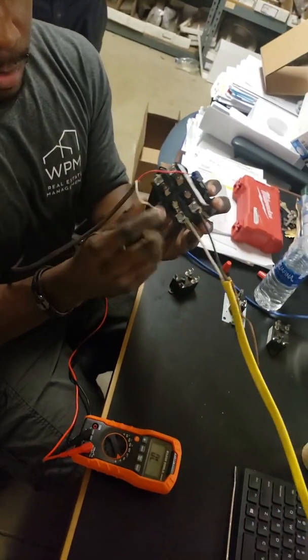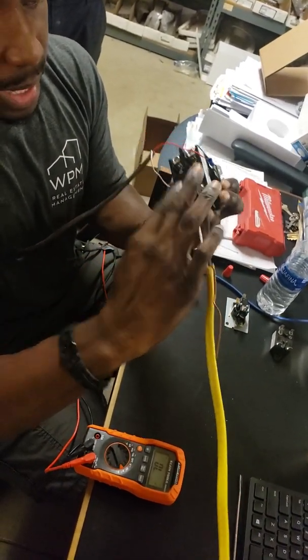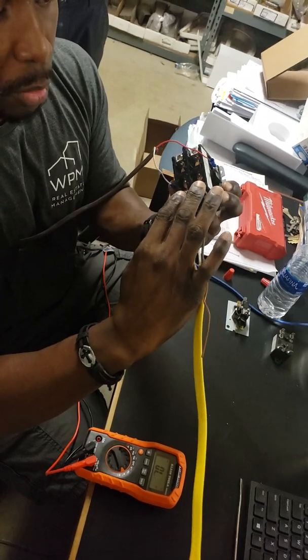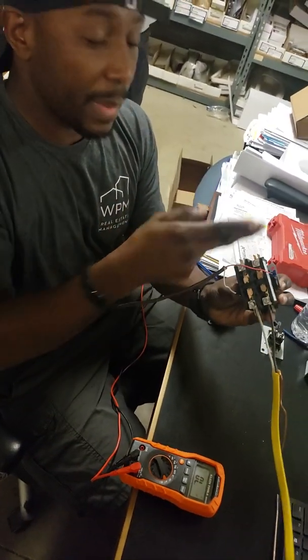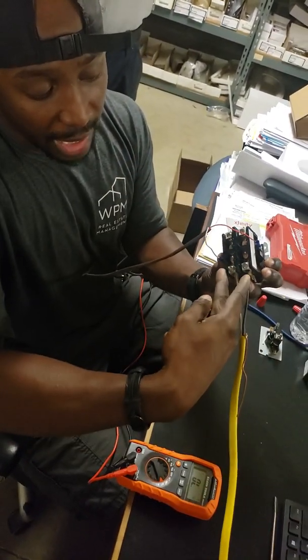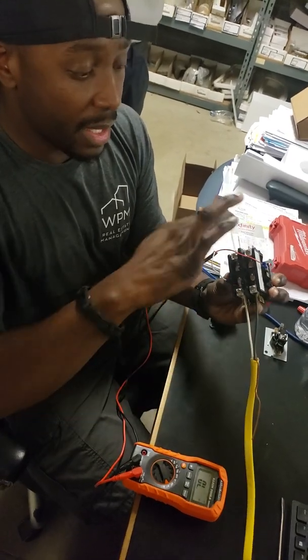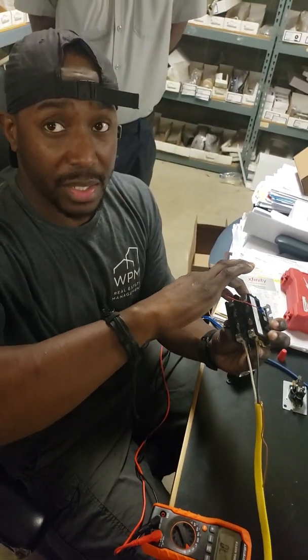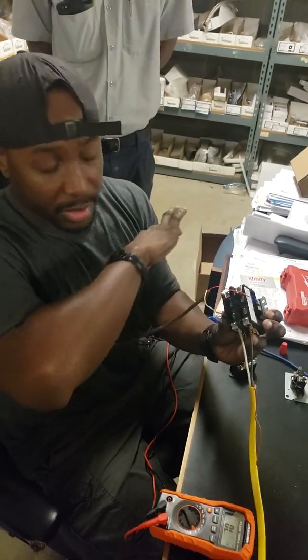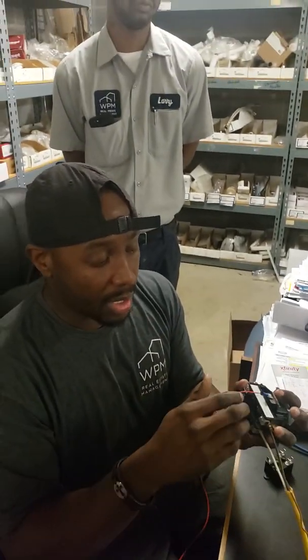With that contactor being pulled in, it sends voltage from here to here. So now the 120 volts that was only on this side is now coming out of this side. This is considered your line, that's the feed of the electricity. This is considered the load, whatever you're trying to control, coming off of the contactor. Okay, so that's pretty much how a contactor works.